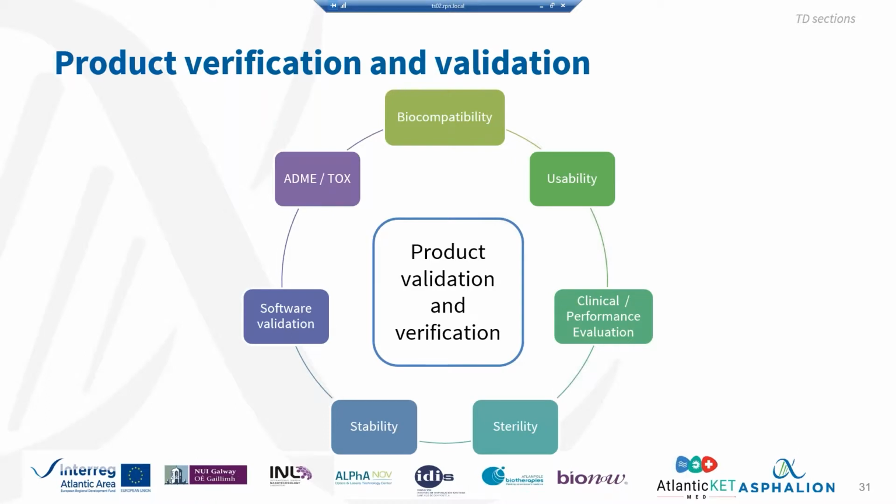Okay, this is particularly important in two cases. In medical devices, for substance-based products, this is quite important. And in the case of in vitro devices, in the reagents of the reaction. If you've got several reagents, you've got to make sure that they're stable in several conditions. Okay. In case they're not stable in normal conditions, you should write it down in the label and the instructions for use of your device, so that the user knows how to store this device so that it keeps stable.